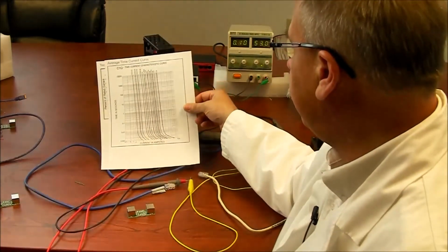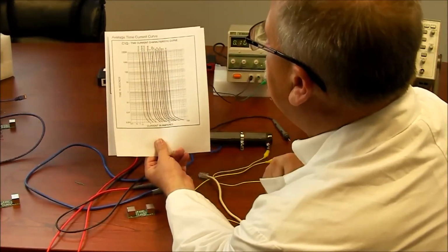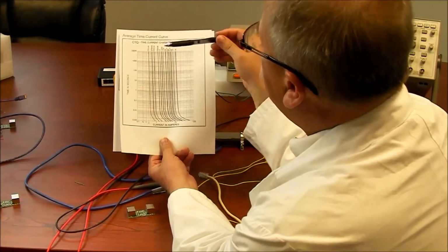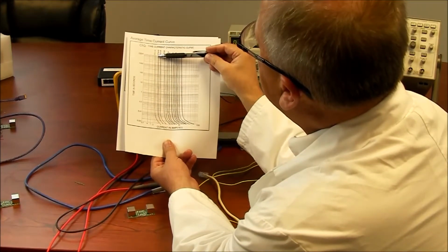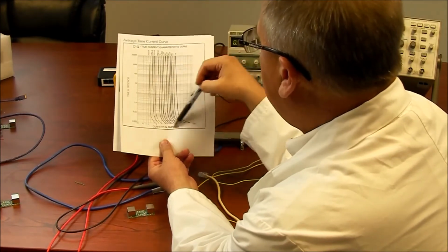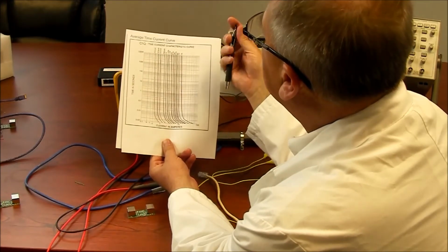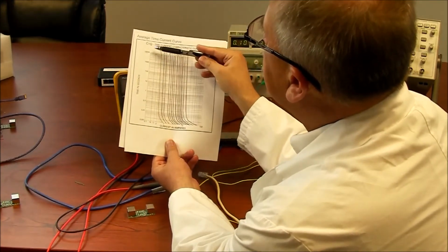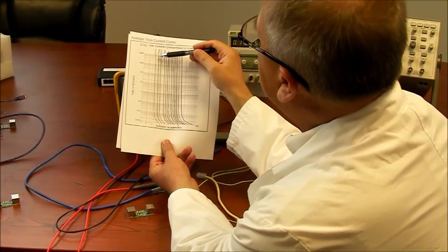Here's the other crazy curve, though. This is their curves for, well, when's this 375 milliamp fuse going to blow, okay? So what we've got here is a scale across the bottom in amps, right? It's a logarithmic scale, and this is how many seconds you've let it run. Well, I've let them run a lot more than 10,000 seconds over here on the side.